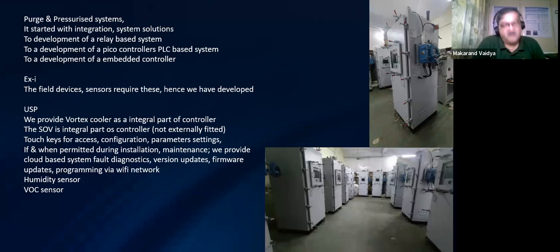Now, how did VOC come into this? These control panels are in hazardous areas, so there is a hazardous, flammable mixture in the surroundings, and leakages are always possible inside as well. At the same time, the polymer components of the control panel hardware - cable trays, cables, contactors, everything - deteriorate because of ambient conditions, and they can release volatile organic compounds. These are also a cause of fire and flame.